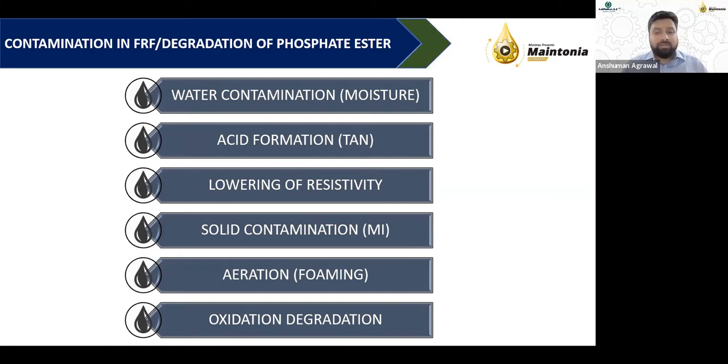The unfortunate thing is that when water is present in the fluid along with copper, iron, and other metal contaminants, this entire process is accelerated. It finds a unique favorable condition around it, because these metal ions start acting as catalysts towards that reaction.